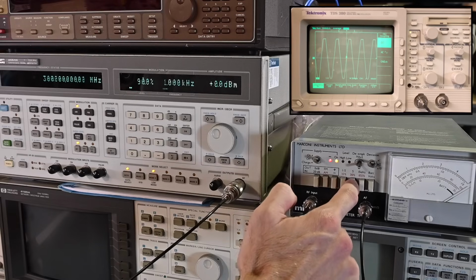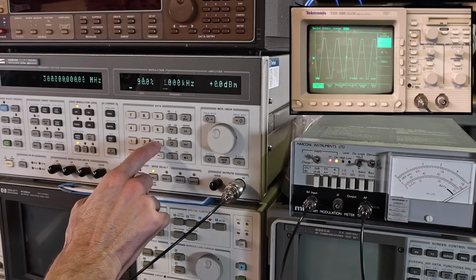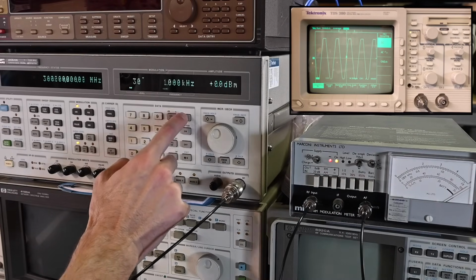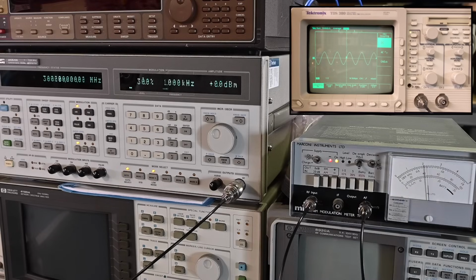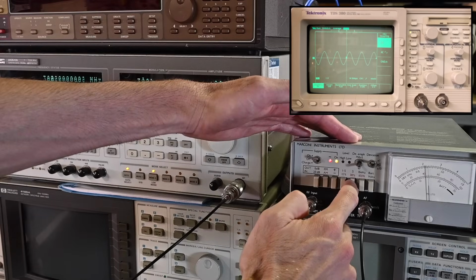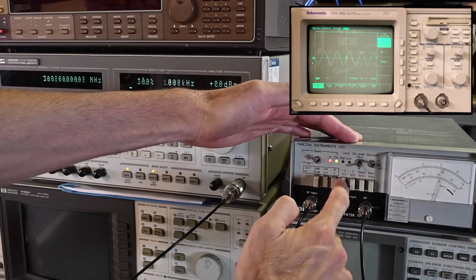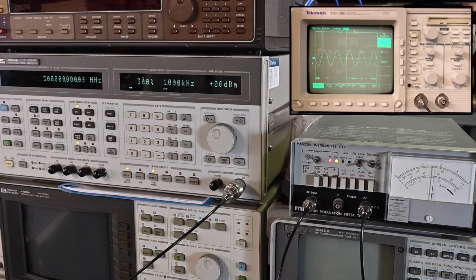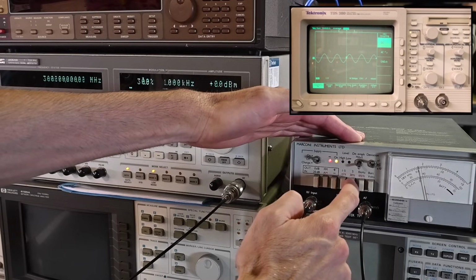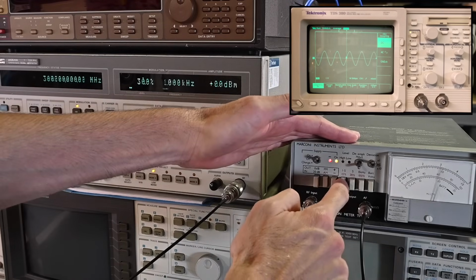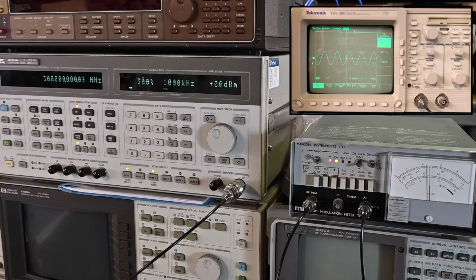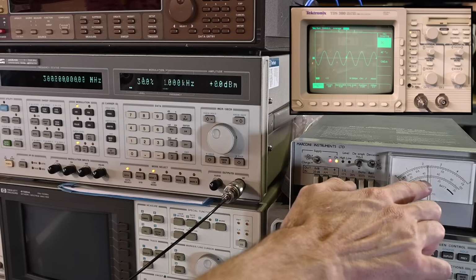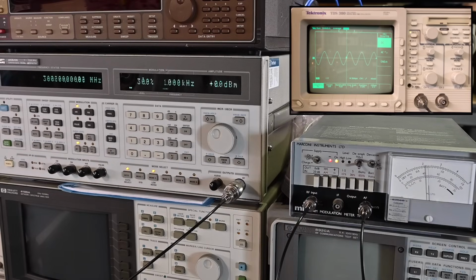Also, as I'm pushing this button here, let me just go back down, say 30%. I don't think it's an intermittent connection on this switch, because I've tried pushing this — if I jump around on those ranges, it doesn't really change that. I don't think it's switch contact problems. I've pushed the switches in and out a number of times, and I don't get the feeling it's a switch contact issue. It does look like somewhat of an intermittent connection, though, because look how that's jumping around — it's not steady at all, whereas it is steady in the other ranges.